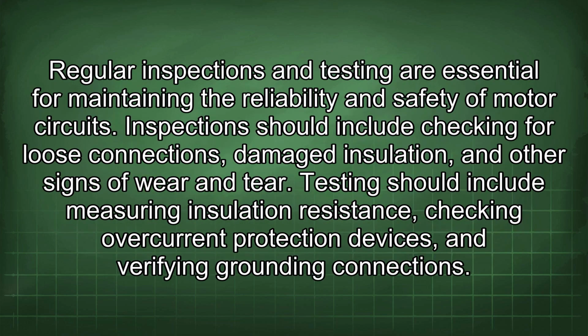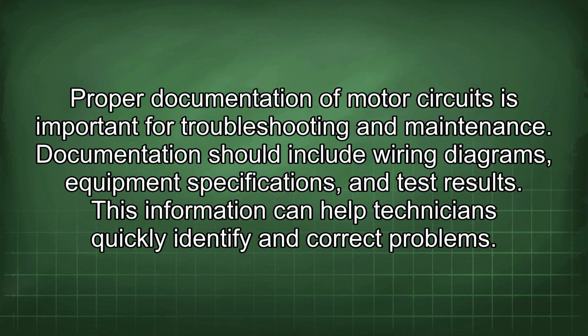Regular inspections and testing are essential for maintaining the reliability and safety of motor circuits. Inspections should include checking for loose connections, damaged insulation, and other signs of wear and tear. Testing should include measuring insulation resistance, checking overcurrent protection devices, and verifying grounding connections. Proper documentation of motor circuits is important for troubleshooting and maintenance. Documentation should include wiring diagrams, equipment specifications, and test results. This information can help technicians quickly identify and correct problems.